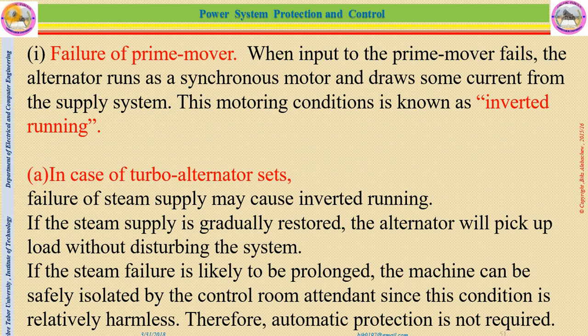Now let us see failure of prime mover. When the input to the prime mover fails, the alternator runs as a synchronous motor and draws some current from the supply system. This is called motoring condition or inverted running. That means it converts from generator state to motor state. It may be considered for different types of generator. For example, in the case of turbo alternators, the failure of steam supply may cause inverted running, and if the steam supply is gradually restored, the alternator will pick up load without any disturbance of the system.